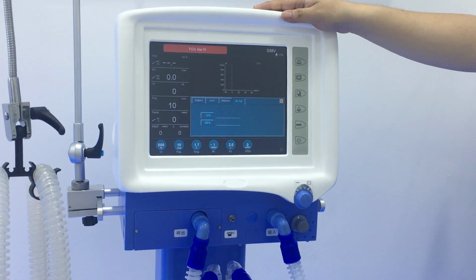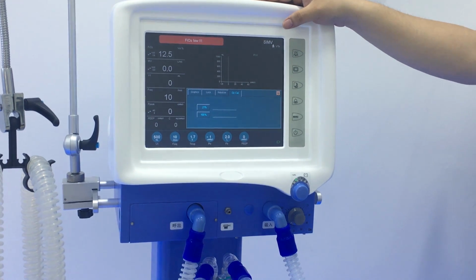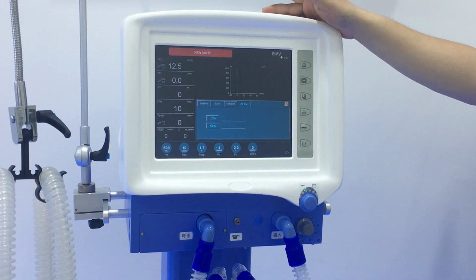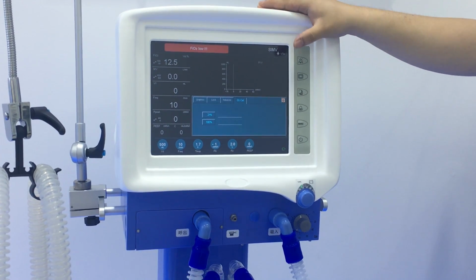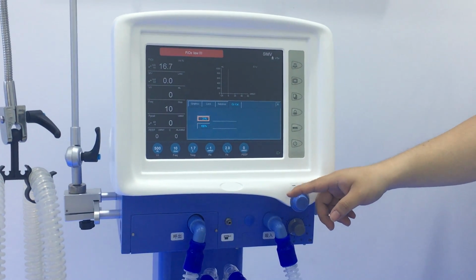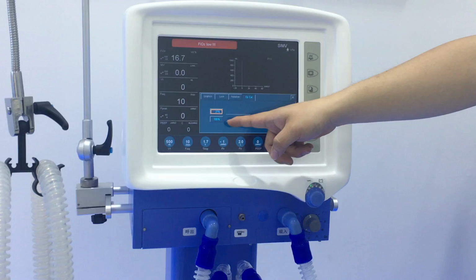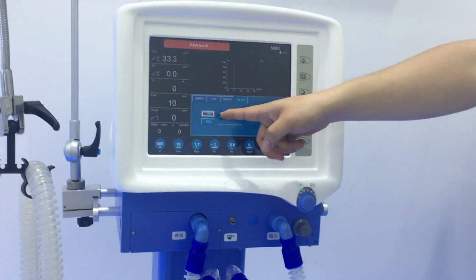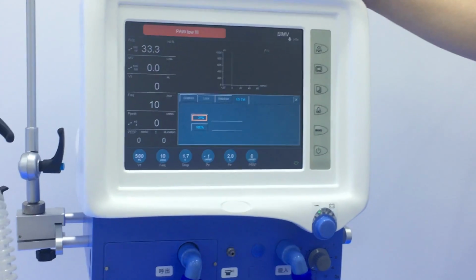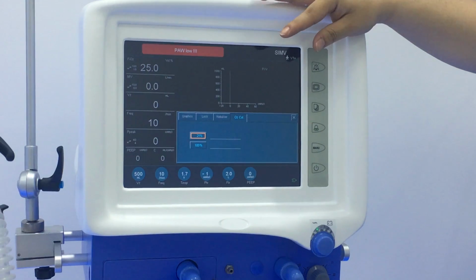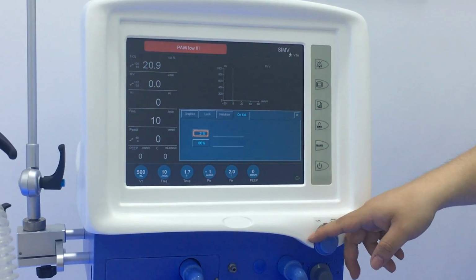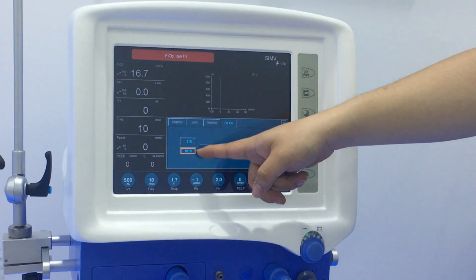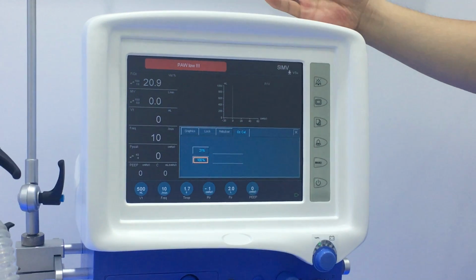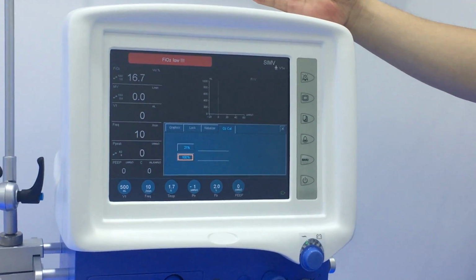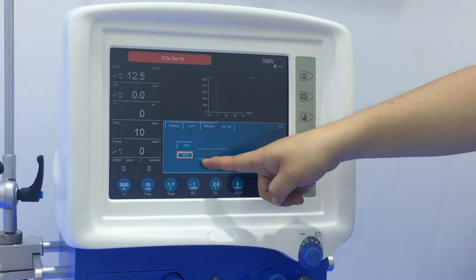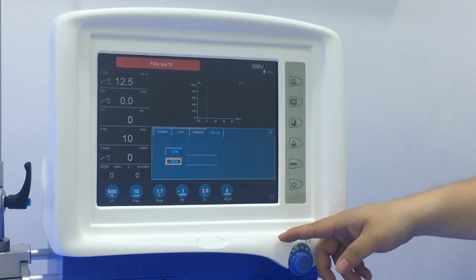So for oxygen calibration, actually, when you first get the machine, you don't need to do the calibration. Only if after 2 or 3 years or more years, you think the parameters is not very accurate, then we will do the oxygen calibration. And first, here we can see there are 2 points. One is for the 21% point, and another one is the 100% point. At the 21% point, you just only connect with the air and no oxygen source, and you do it. And after 2 minutes, here we are showing completed. Then we turn to the 100%. For 100% calibration, we take out the air source and only connect with the oxygen source for pure oxygen. And then we do the 100% calibration. And when it is also completed, then all the calibration will be finished.